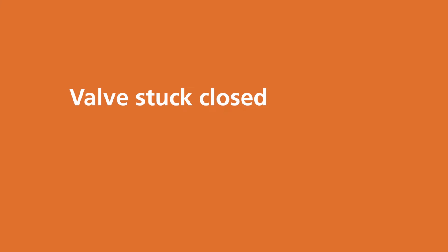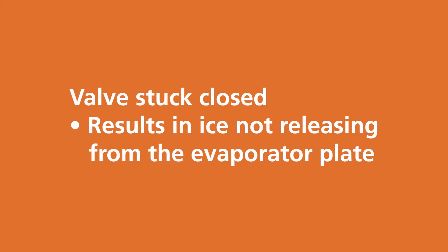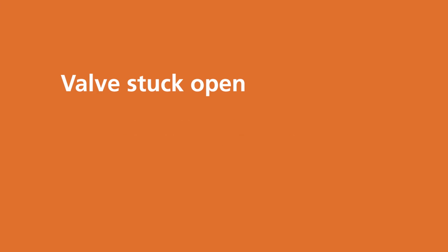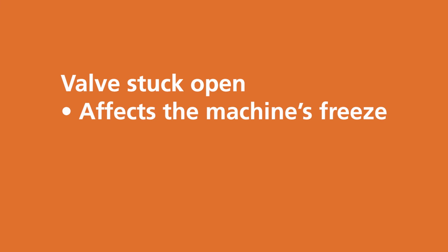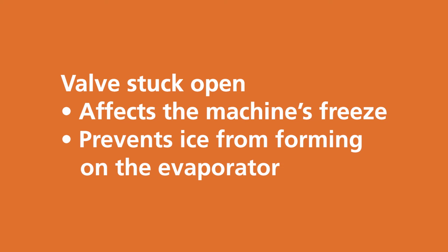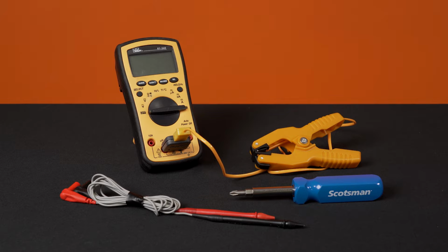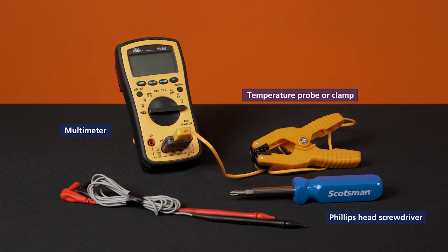First, the valve may get stuck closed, which would result in ice not releasing from the evaporator plate. Second, the hot gas valve may get stuck open, affecting the machine's freeze and preventing ice from forming on the evaporator. The tools required for this test are a Phillips head screwdriver, a multimeter, and a temperature probe or clamp.